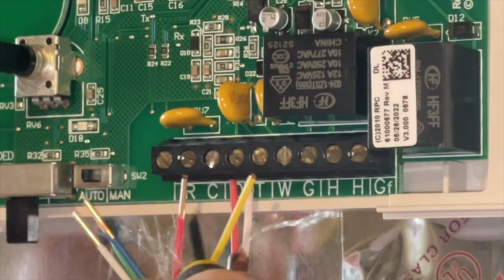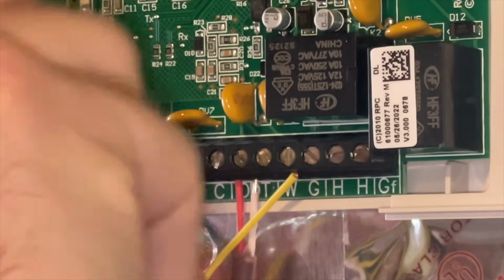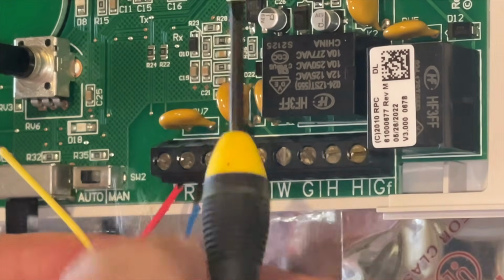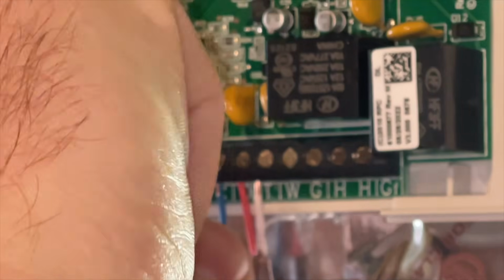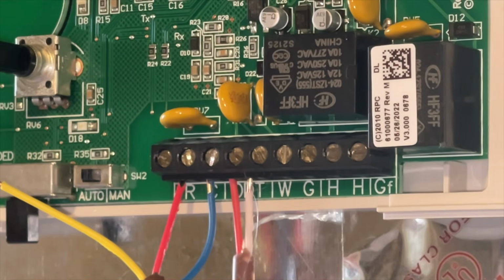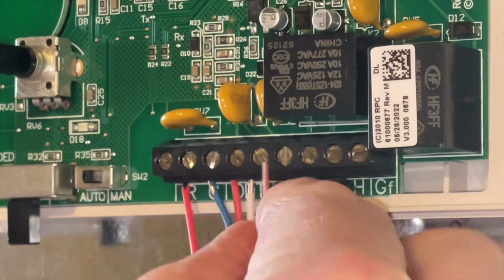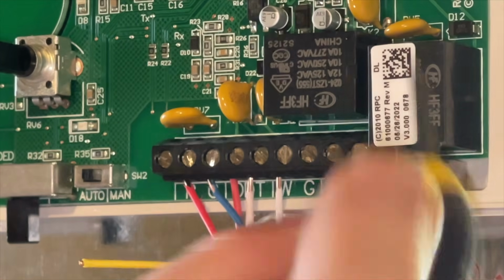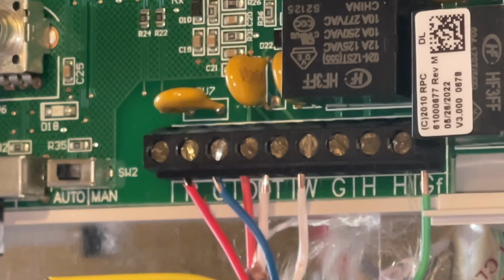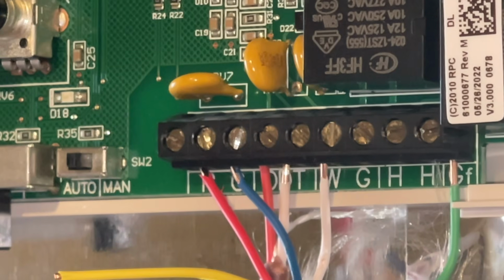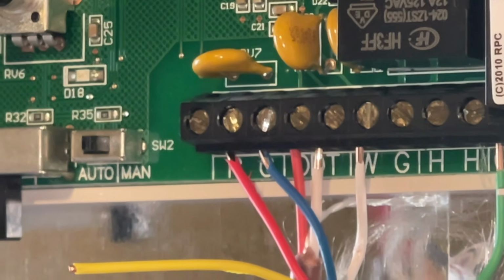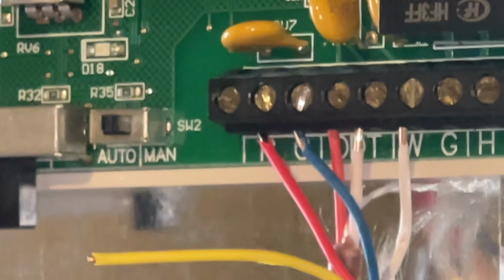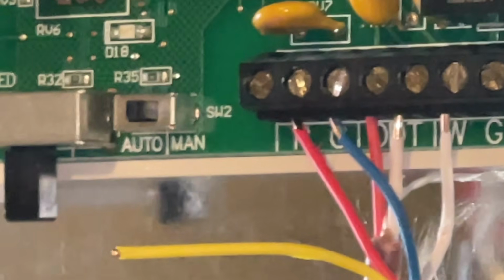Next, we want to attach the 5-wire cable to the humidistat. Working from left to right, we're going to hook up the red wire to the R, the blue wire to the C, the white wire to W, and the green wire to GF. The yellow hooks up to the thermostat control, but with the spacing and the distance, I'm not able to run this, so we're just going to leave that out.